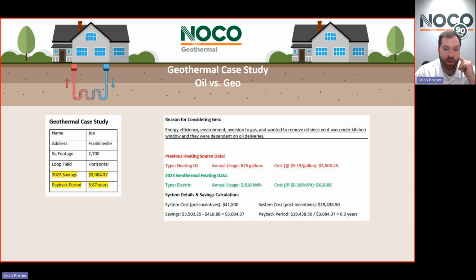Considering that $19,000 Geo system was about 6 grand, 7 grand more than he would have paid for a high efficiency total boiler replacement, but let's just call it 10 grand. Let's just say it's 10 grand more than he needed to spend. Well, saving $3,000 a year puts his payback period at about 3 years for that overage. His payback period on the system overall, assuming he didn't need to replace it at all, let's just call that whole $20,000 on Geo a sunk cost, is only about 6 years. He's saving so much money that the overage he spent on Geo is easily justifiable. And now as he goes through the next few decades of heating, he's going to have a continued obscene amount of savings because he's not going to be spending 3-4 grand a year on heating anymore.